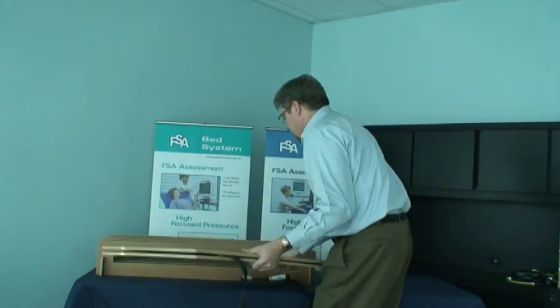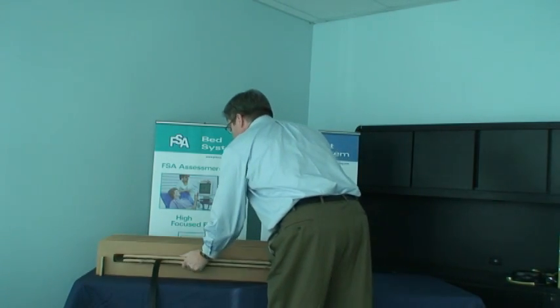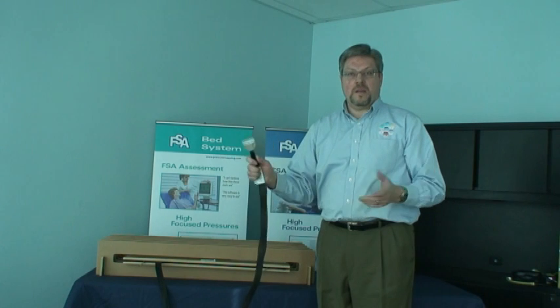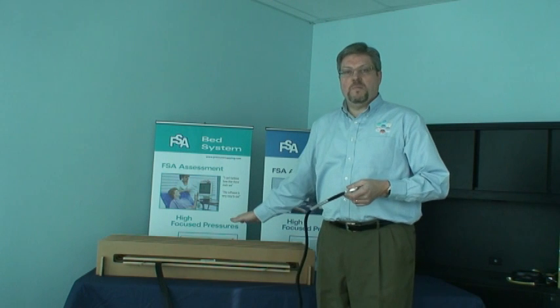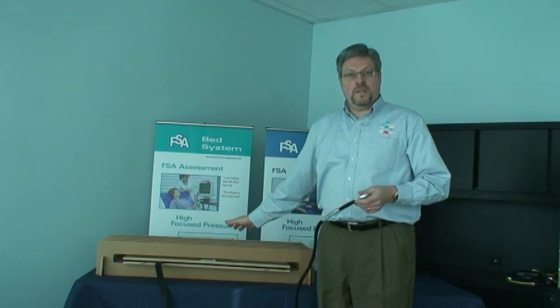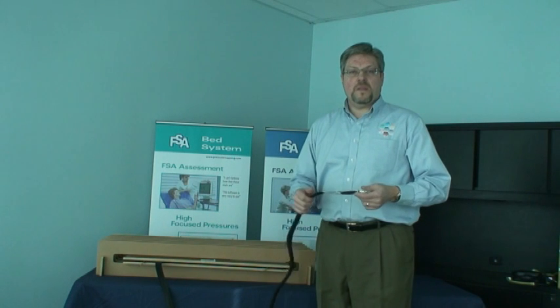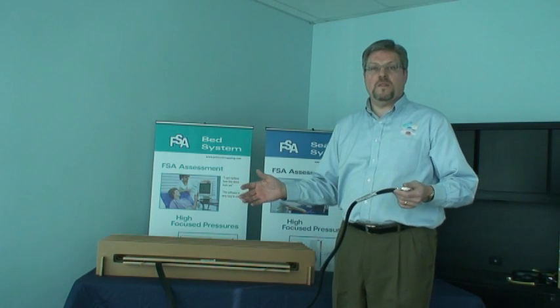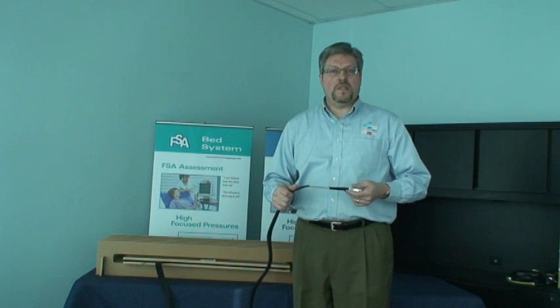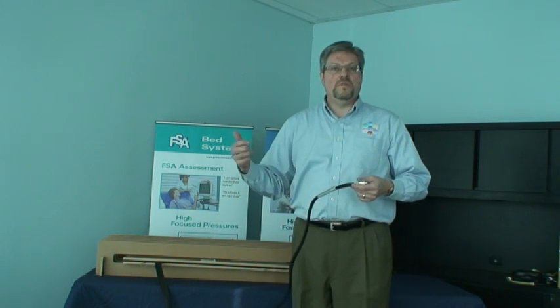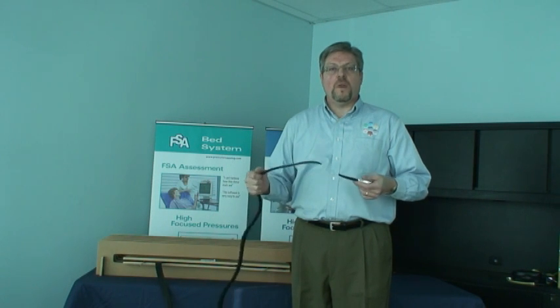You take this whole assembly and slide it inside the calibration kit. And if you're doing one mat, a seat mat, this would plug into your A port on your Type 4 interface module, and then of course that's connected to your computer. So once you've actually built the calibration assembly and are ready to start inflating, that's time to get the FSA 4 launched. Best protocol to follow is to power up the interface module, make sure you have a red and green light flashing on the front of it, then launch the software, and that should bring you to the software right away. Go to Tools, Calibration, and follow the instructions for a pressurized calibration.